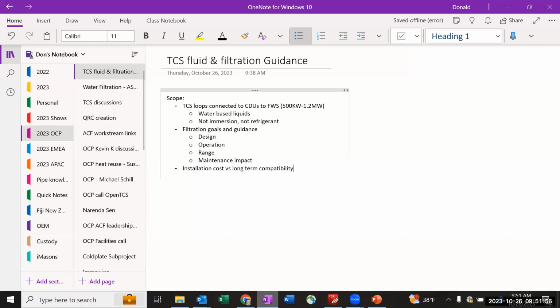And if they haven't, you need this laundry list for everything that's in the IT coolant loop that could challenge your move to go from, say, 100 micron to 25 micron coolant. And it even depends on whether the filtering system inside the CDU is capable of accepting a 25 micron filter.